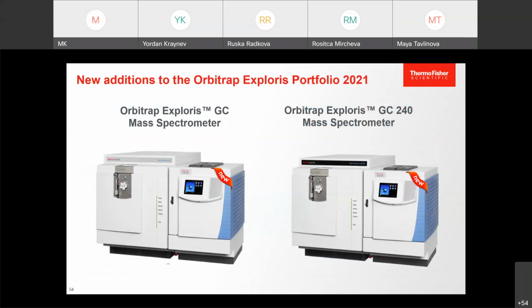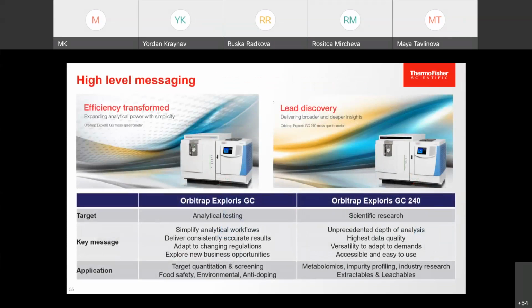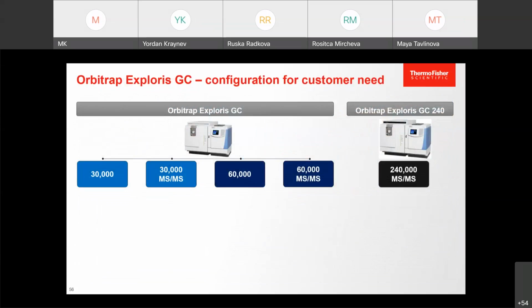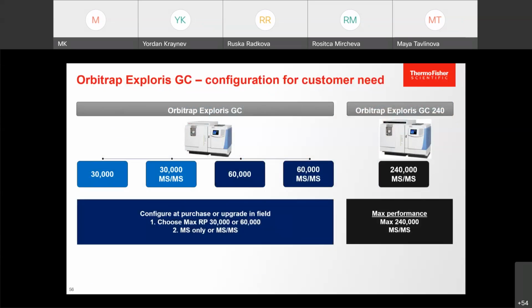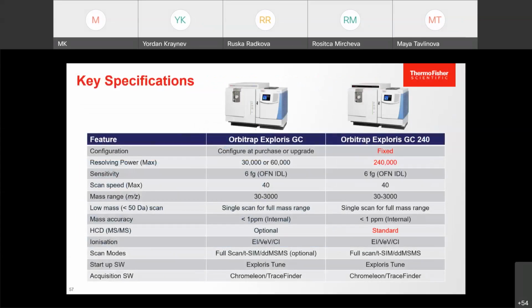And last one but not least, this year we introduced and replaced all Exactive and Q Exactive with Orbitrap Exploris 120 and Orbitrap Exploris 240. You can see where we are using Exploris: analyzing, testing, scientific research, high data, metabolomics, all information. If you need, you can just write me an email. I can give you a webinar only about the Orbitrap Exploris instrument. You can upgrade from 30,000 to 60,000 resolution MS, and 240 is fixed. You cannot change this. And if you look at Orbitrap key specification, you can see Orbitrap Exploris GC 240 means 240,000 resolving power, the maximum which we can do. Sensitivity is 6 femtograms, and you can see all information about this instrument.